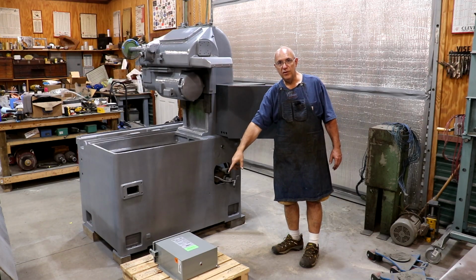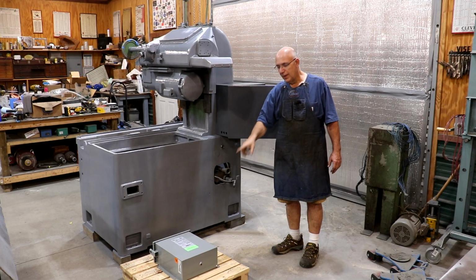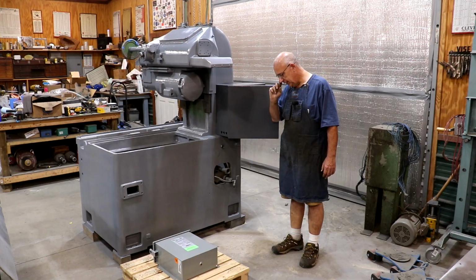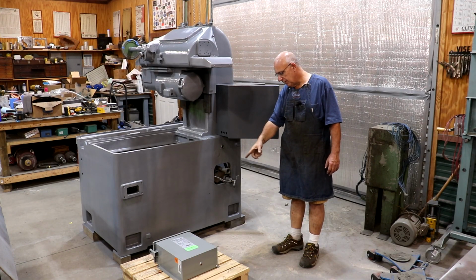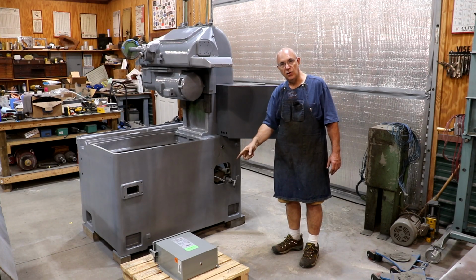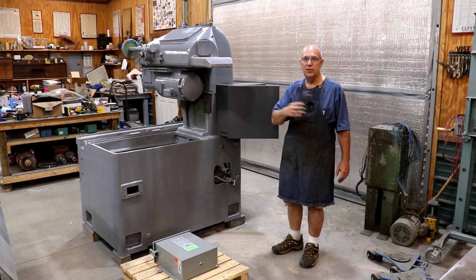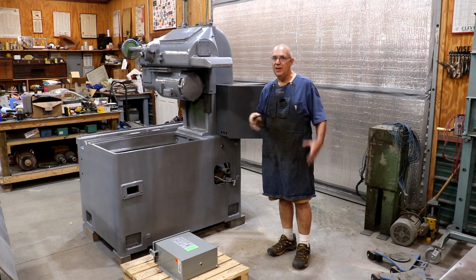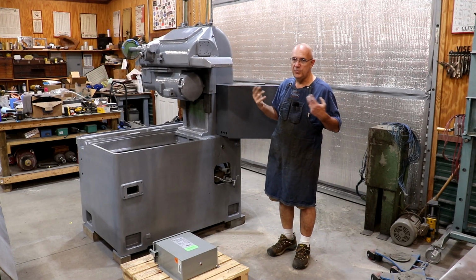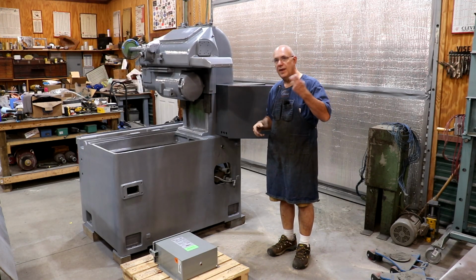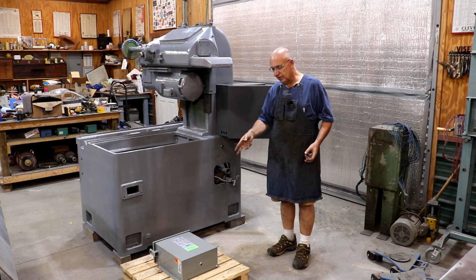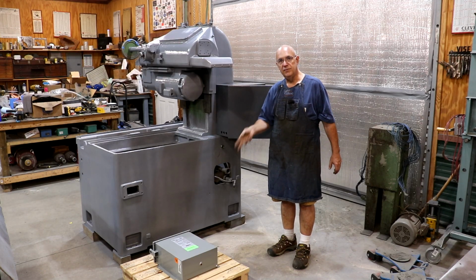Down here on the floor in front of me is a transformer I picked up. This is basically a multi-port, multi-tap transformer, and it has the ability to take 220 volt 3-phase and convert that to 440 volts. It's the same way the power company does it - you put transformers in to step voltage up and down all the time, and that's exactly what we're going to do with this. We're going to give it the 220 volts.